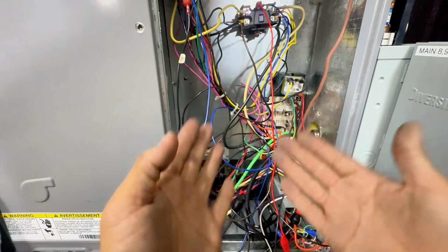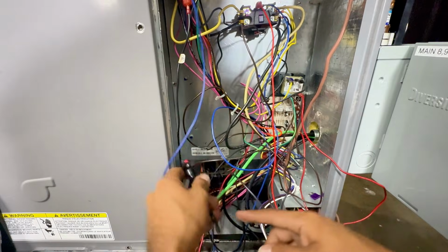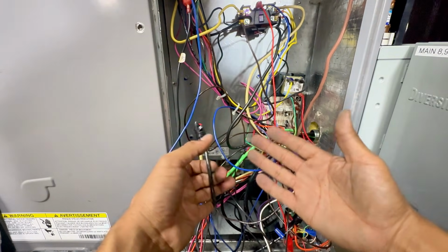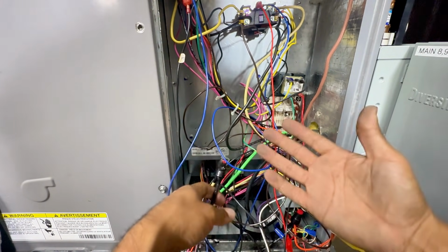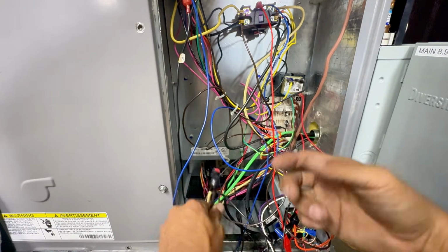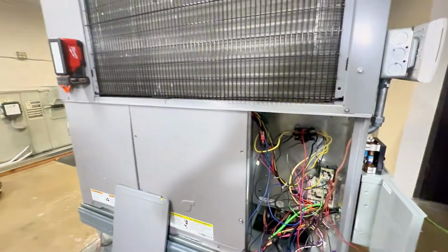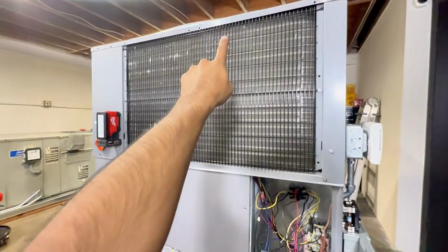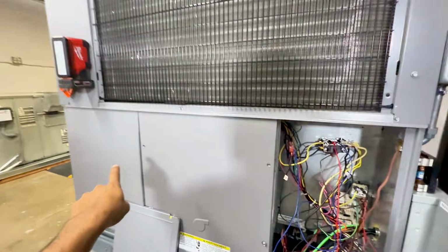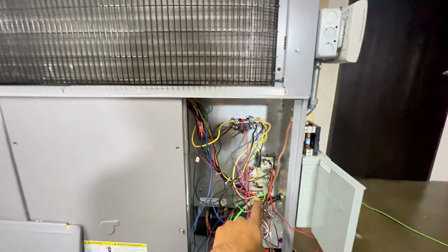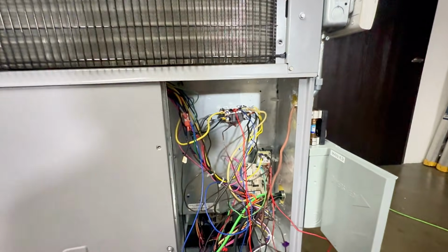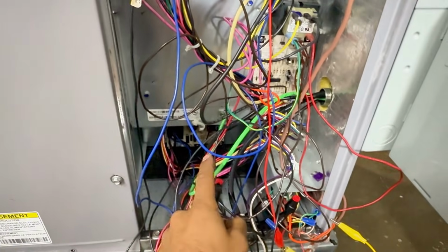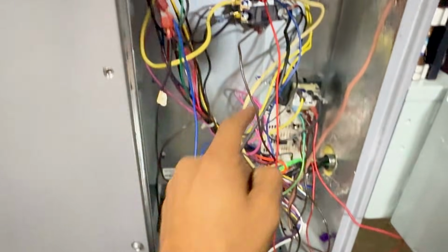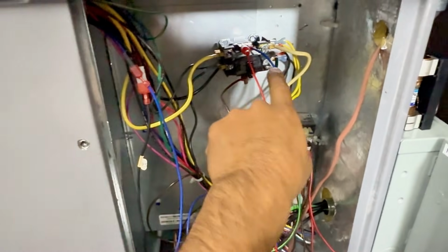And one thing you can also do is check the amp draw on one of the legs coming in. So this is a single phase 208 volt system. So you've got 2 hot legs and a ground. Isn't it true though, when you think about it, all the loads, condenser fan motor, your indoor motor, your compressor, your thermostat, your transformer, your contactor coil, all that, you can add it up basically by checking one hot leg. And the one that I would check would be the one going to my common on this side.